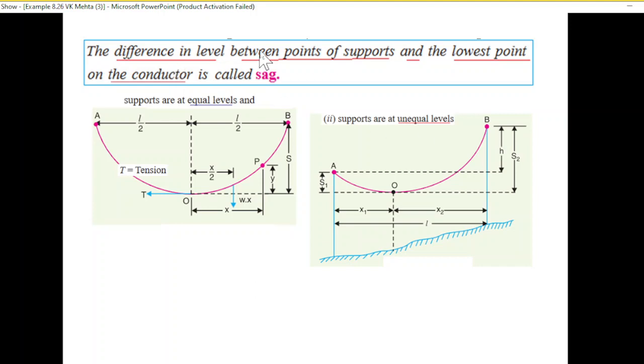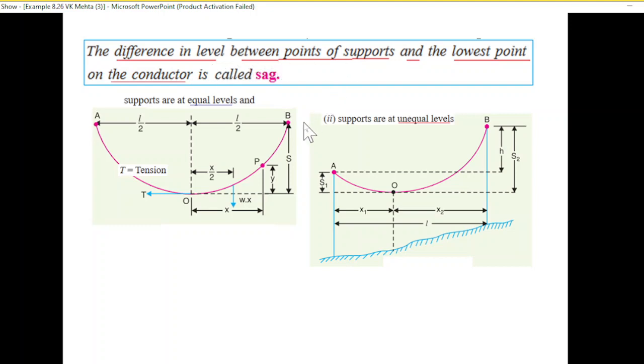The difference in level between points of support and the lowest point of the conductor is called sag. In this case, A and B are the two support points (pillars). The difference in level between the point of support B and the lowest point on the conductor is called sag. For unequal supports, the sag closer to the lower support is s1 and the sag closer to the higher support is s2.